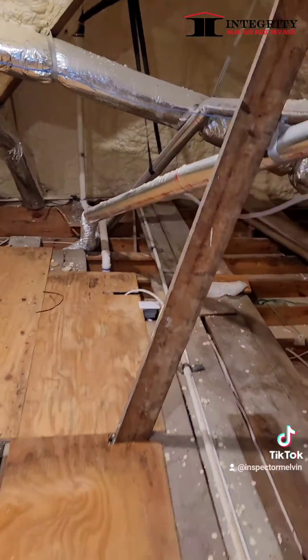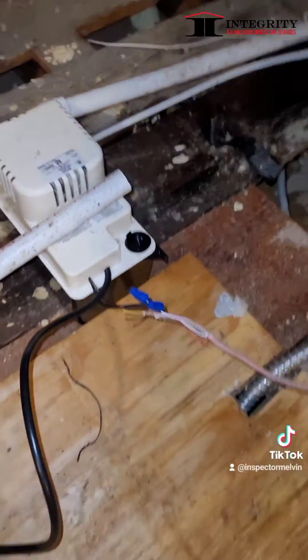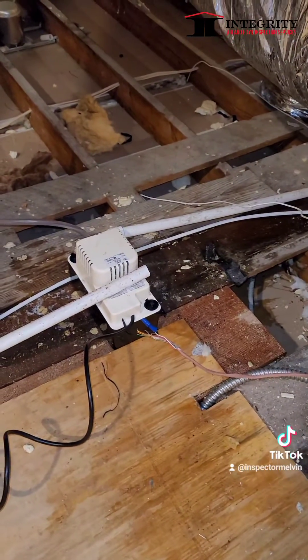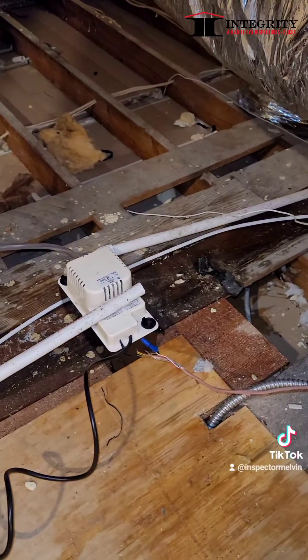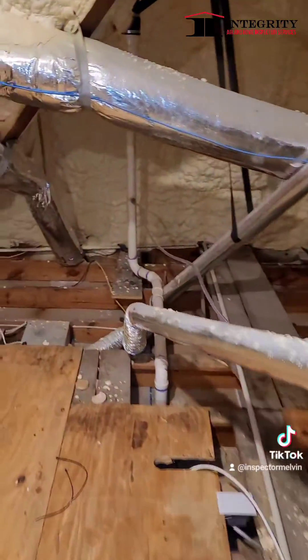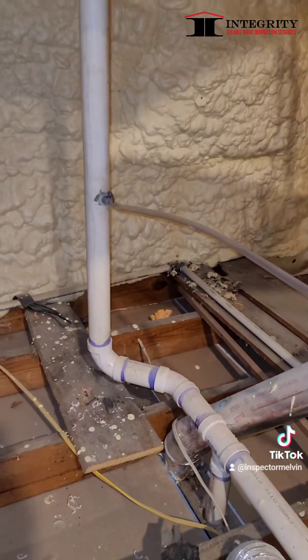What I did was, in order to get them some heat, I cut the drain here. That's the original pipe — put in the condensation pump, made sure I wired it in. Somebody's going to say something about a pan. I don't have a pan on the truck, it's Christmas Eve, we can't get a drain pan, so I can't put a drain pan on it. But I did put a safety wire in there, got a GFCI switch here, and I ran this vinyl tubing down to the drain pipe. I was going to run it to the bathroom temporarily, but anytime you can avoid running drains through customer homes, you want to try to do that.